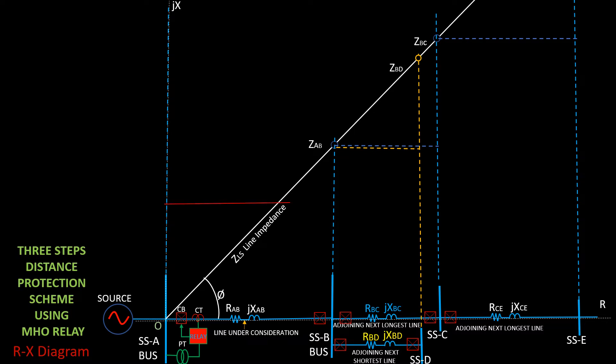Zone one protection: eighty percent of line length between substation A and substation B. Twenty percent is unprotected by zone one. Z1 is the impedance of the protected zone 1.